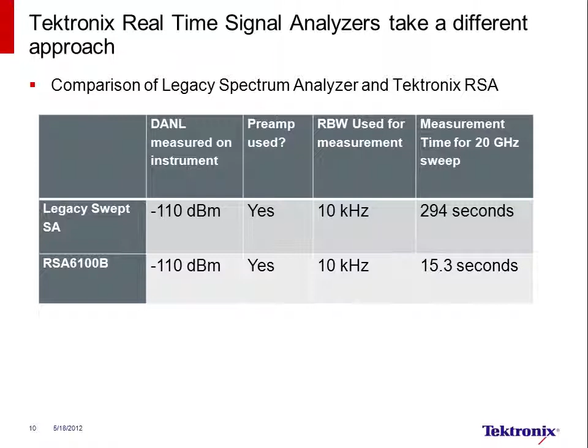One of the unique capabilities of the RSA is swept DPX. This allows the instrument to examine 110 MHz bandwidth of spectrum at a time to achieve a wideband sweep of the entire 20 GHz frequency range. The DPX capability is powered by a dedicated FPGA where the instrument's real-time capabilities are enabled. The FPGA performs at a rate of over 292,000 FFTs per second and can display them in a number of ways.